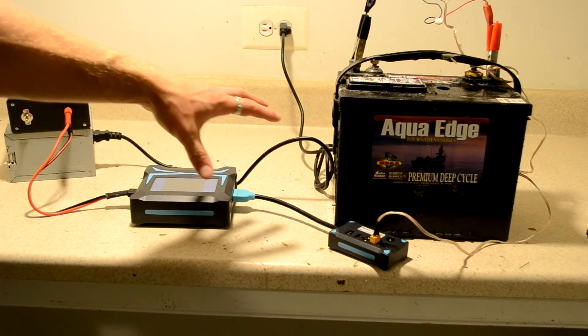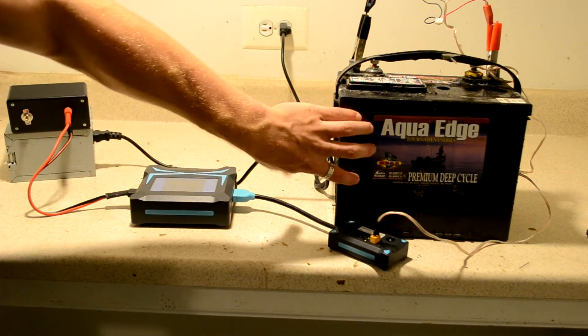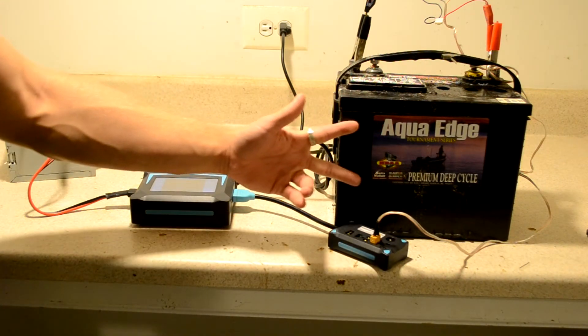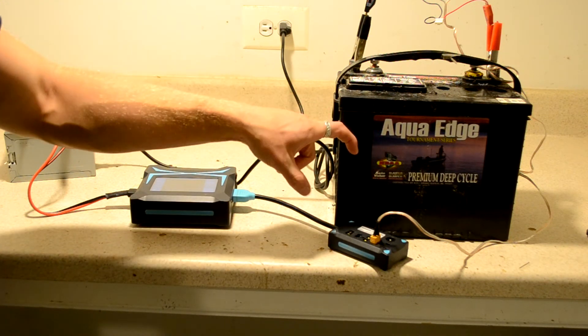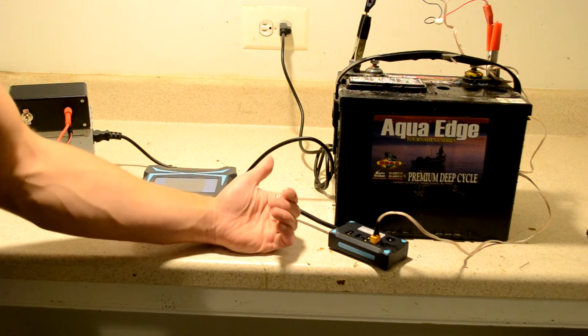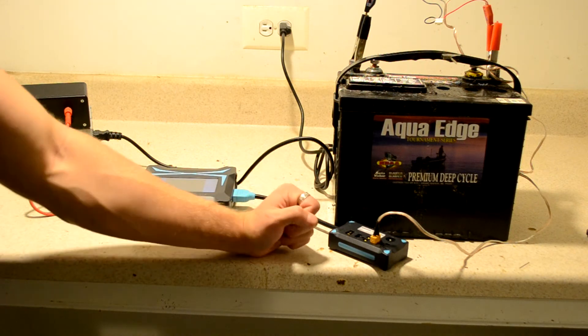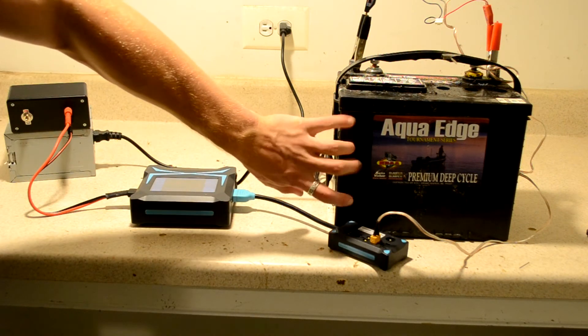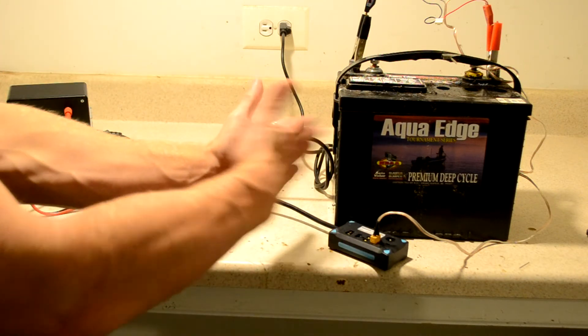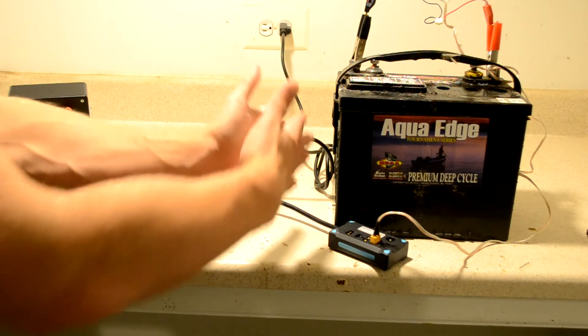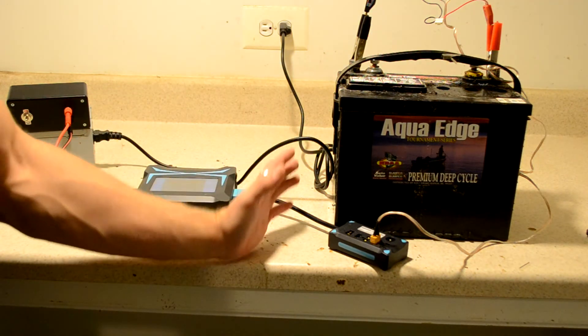Well, that's very simple. The whole operating principle of this battery is that the sulfuric acid acts as an electrolyte and needs to make an ion transfer between the two plates in the battery. And what will sometimes happen, if these batteries are left in a very low state of charge, is that sulfates, compounds of sulfur and oxygen, will build up on the lead plates, and they do not conduct electricity.